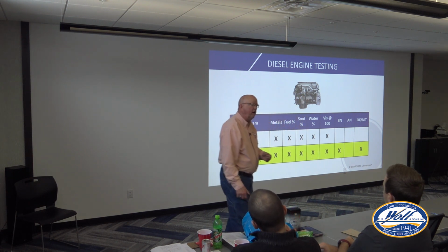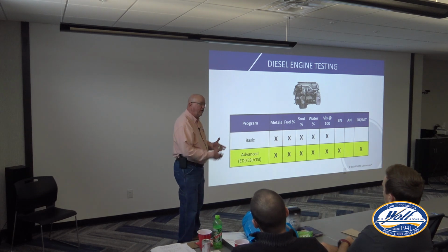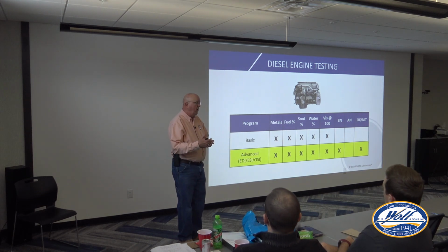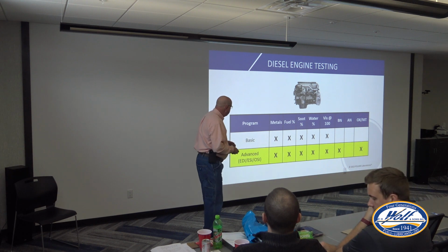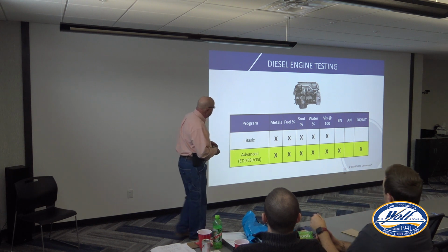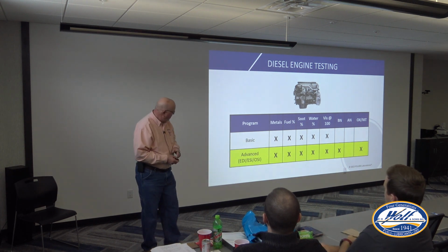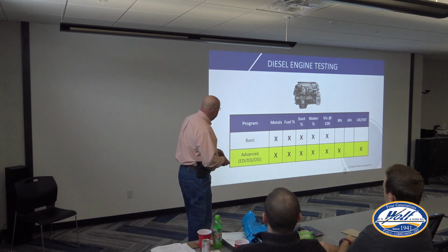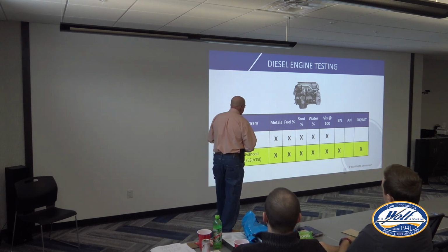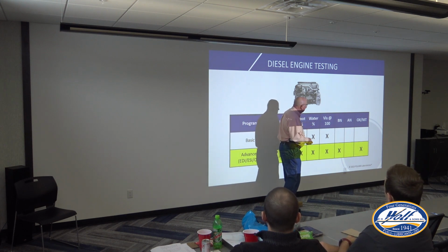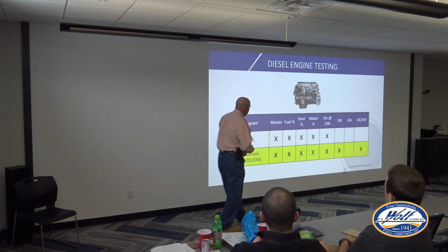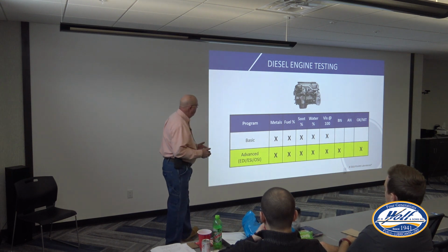Believe it or not, we actually have some customers that we start with, and we say, you know what, you're overextending that oil. You need to shorten your interval. So that does happen. We want to find that optimum service interval. What's that sweet spot for your application? So those are the differences of the test packages. Typically, we're always going to do metals, water, and viscosity on all these tests, whether it's basic or advanced. You're going to hear me saying that over and over.